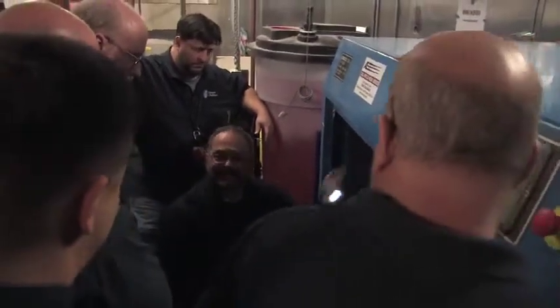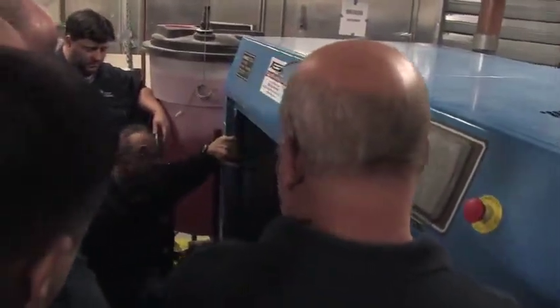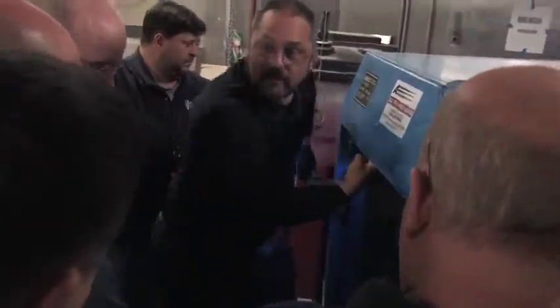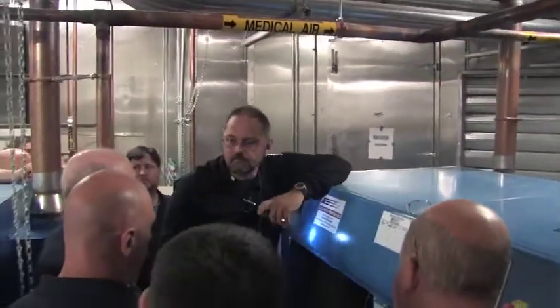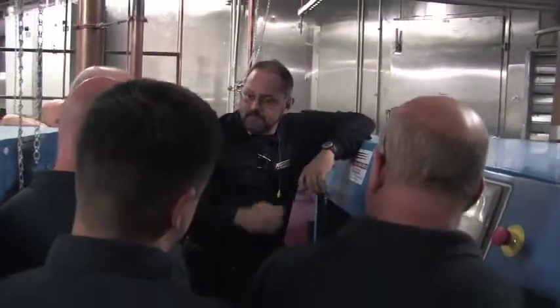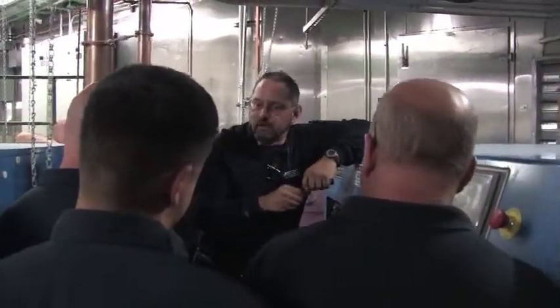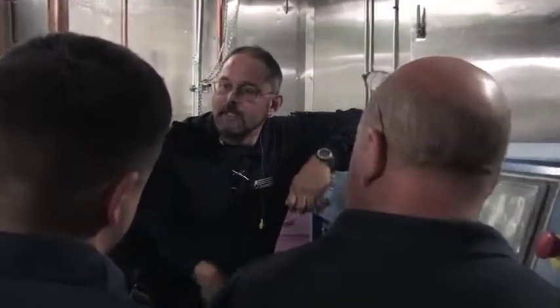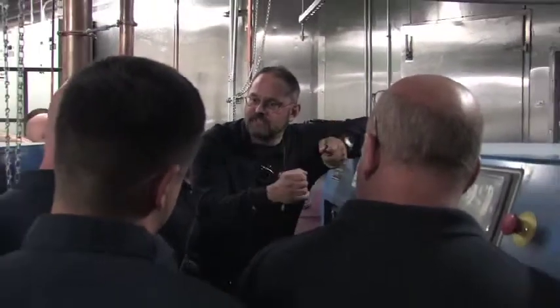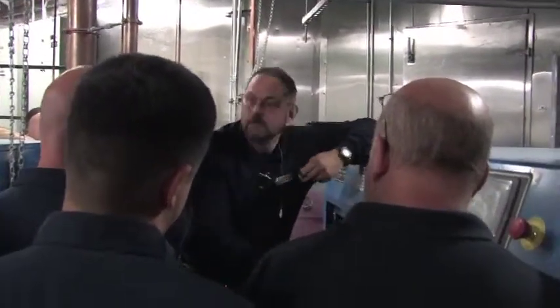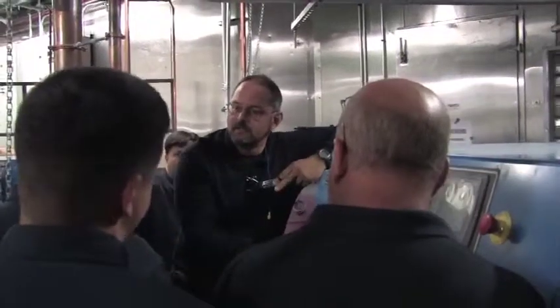Because if you run these backwards more than about 30 to 40 seconds... Really? Yeah, that 600 degree heat that gets pushed one way in here, it gets pushed the other way. Guess what catches fire? Oh, awesome. We had a guy with a 350 horse that caught fire that way. They did some work on it and they reversed it, and did not realize that it was. They did some internal work and changed the motor out. They did it themselves. And well, whoever rewound the motor wound it the opposite way. So when they hooked the leads up the same way they were before, the windings were opposite.